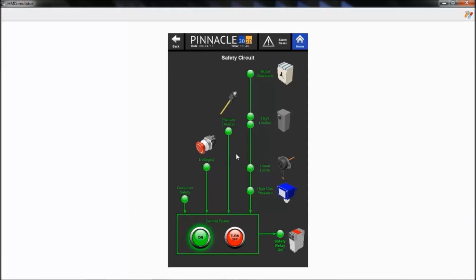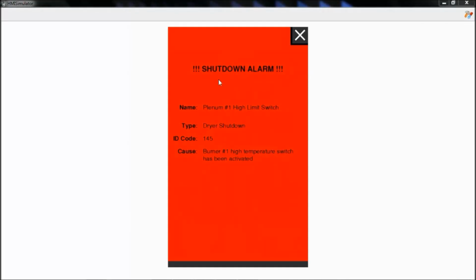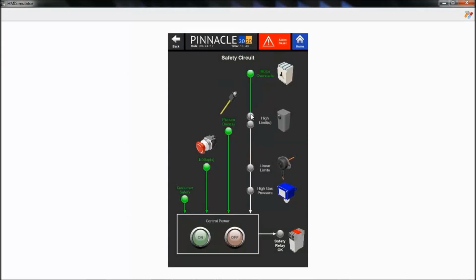So we're going to go through another example here. If we were to trip something on this row, notice that all of these are wired in series. So if we were to lose high limit number 1, we'll see an alarm that says plenum high limit number 1. And you'll notice that all 4 of these lights went out. So when you come to this page, you don't need to check all 4 of these things immediately. You always want to start from the top and work your way down. So these rungs are separate, but these guys are all tied to the same series.